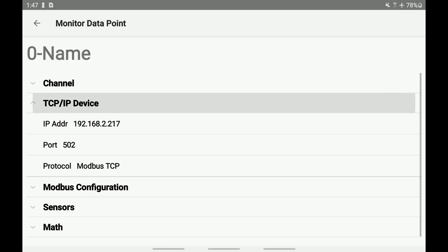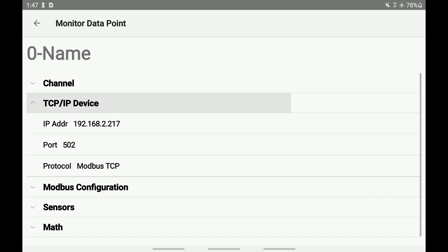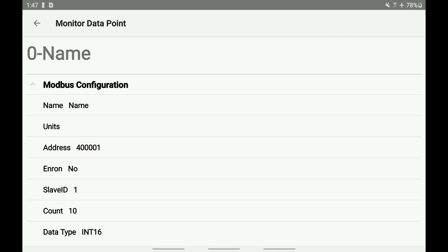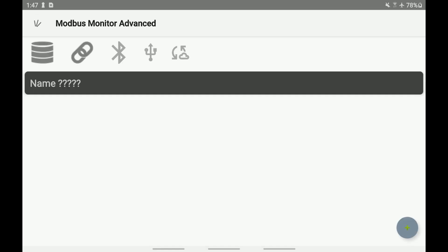Let's check the monitoring point for proper setup. We are using the TCP IP channel, so check the IP address or hostname of the server, port number, and station ID. Enter a number of registers to pull for this monitoring point. We will leave other values to defaults for now.